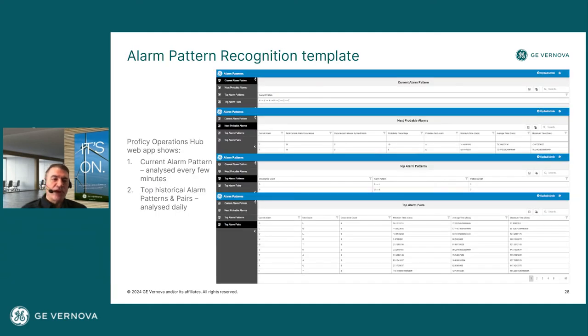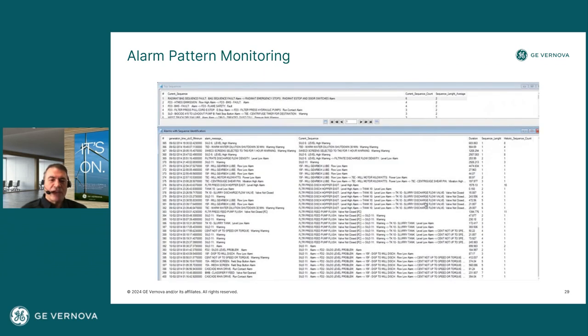Here's an example of the alarm pattern recognition, which shows you the frequency of various alarms and how often they alarm together—various alarms that may be occurring within the system. You can see some of them in this example occurring at higher frequency, so obviously there's a correlation there that can be investigated.